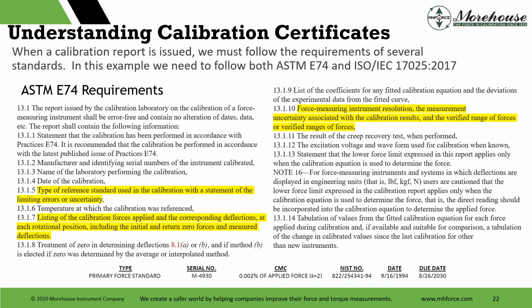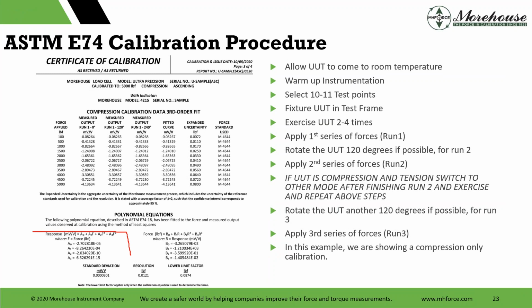And then this is one that trips people up. At least we have some new people in our company, and they say, hey, why do you have this statement on the certificate? And I've had other people say it too, because it's weird. But E74 says, hey, you're going to have to put a statement that the lower force limit expressed in the report applies only when the calibration equation is used to determine the force. It's not you. If you get an E74 calibration certificate, and we'll go to the next page. So what it's basically saying, hey, if I use this equation, this lower limit factor here is good. I cannot go take this device, program it into another meter with a 2-point span, a 5-point span, or something else, and claim that same lower limit factor.